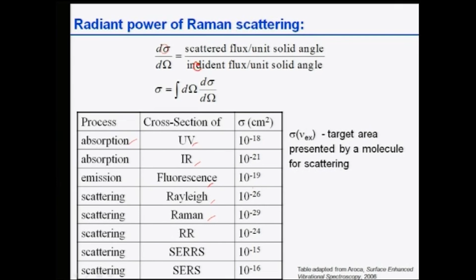So if I have to compare this with other techniques like UV, IR, fluorescence, Rayleigh, Raman, and surface enhanced Raman, you can see the scattering cross section is very high. Very high means not very high, 10 to the minus 18 is pretty low, but still it is high in the case of UV and IR. For Rayleigh and Raman, it is pretty low, 10 to the minus 26, minus 29. That is the problem with Raman spectroscopy, you need a very good detector to detect these scattering events.